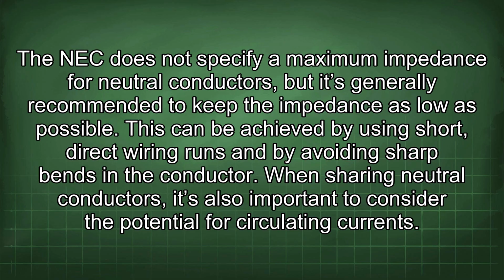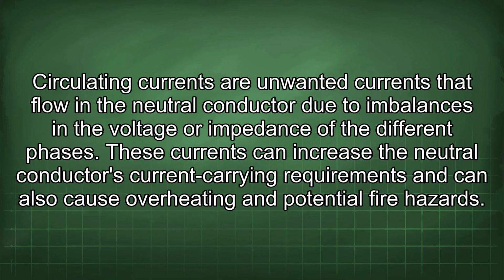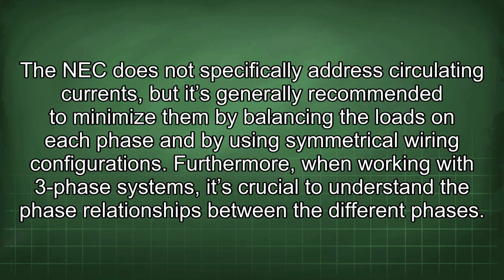the conductor. When sharing neutral conductors, it's also important to consider the potential for circulating currents. Circulating currents are unwanted currents that flow in the neutral conductor due to imbalances in the voltage or impedance of the different phases. These currents can increase the neutral conductor's current carrying requirements and can also cause overheating and potential fire hazards. The NEC does not specifically address circulating currents, but it's generally recommended to minimize them by balancing the loads on each phase and by using symmetrical wiring configurations.